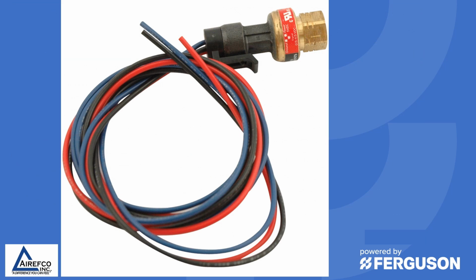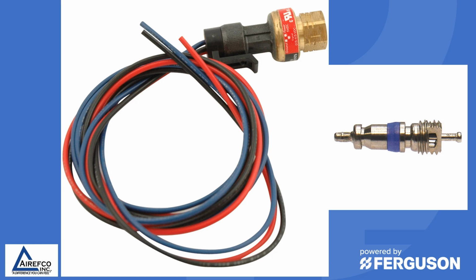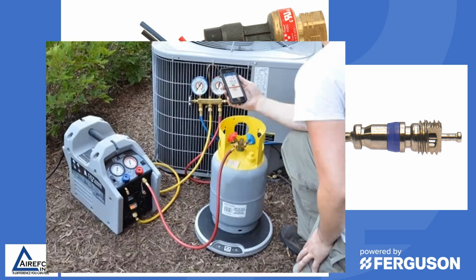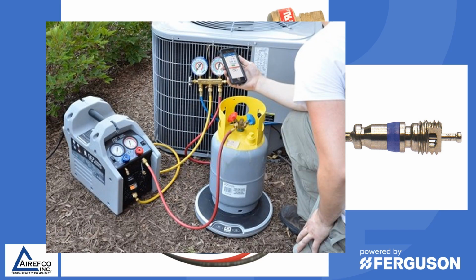Another thing you want to keep in mind, if you do have a defective transducer and you have to change it, these transducers may screw onto a port on the discharge or suction line, but in order to replace them, you have to realize there is no Schrader core behind these transducers. Most manufacturers do not put Schraders behind any safeties or pressure transducers that are on systems. So in order to replace a transducer, you would have to completely recover the entire charge out of the unit, replace the transducer, and then charge the system back up.